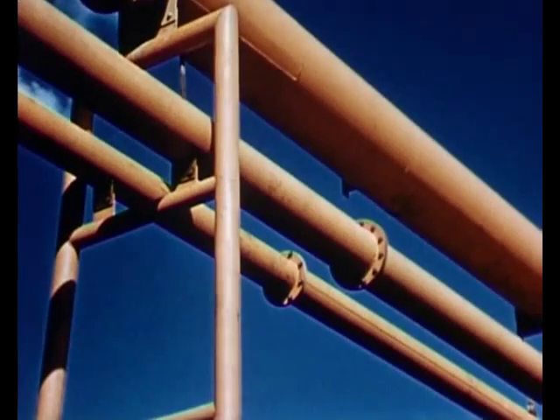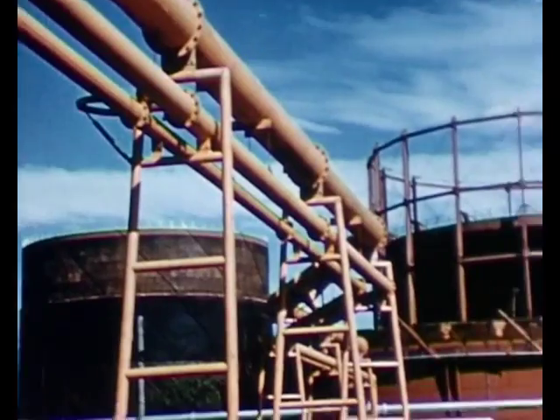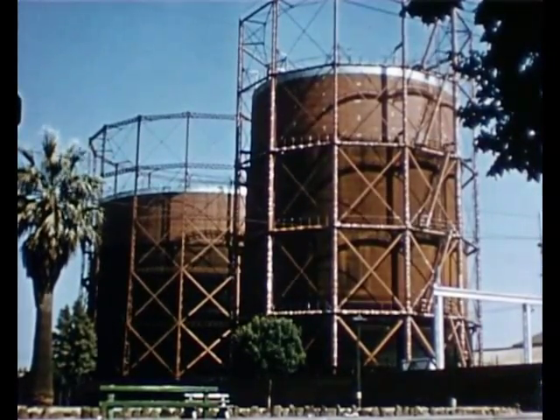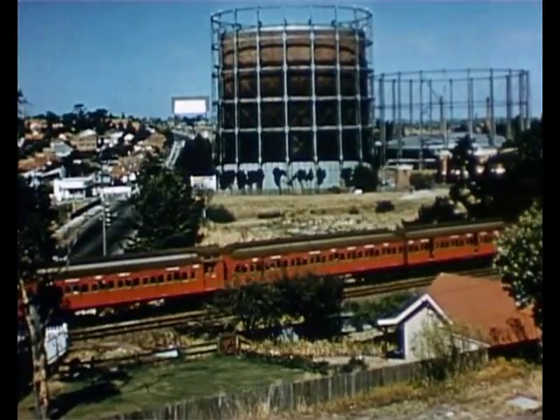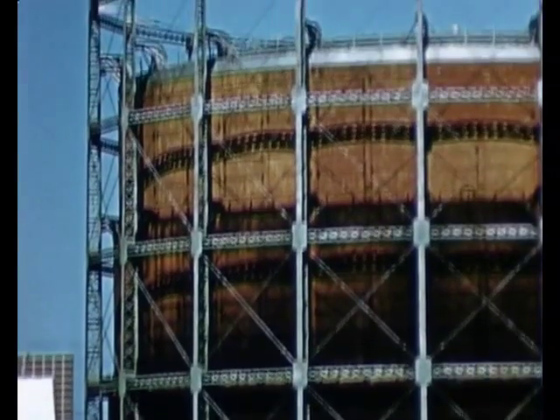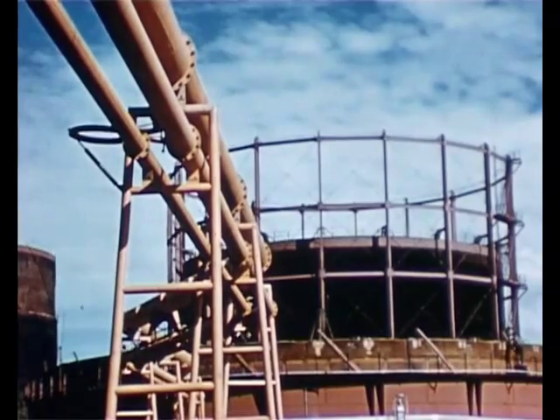The finished gas is piped to these large gas holders, which are the feature of all gas works. Although more gas is used during the peak periods of breakfast and tea time than at any other time of the day, gas is made steadily all through the 24 hours. Both the holders at the works and others in the suburbs hold the gas which is not needed during the slack or off-peak periods of the day and night. This extra gas is then used to meet the big demand at the peak periods. That is why sometimes the holders are full and at other times nearly empty.